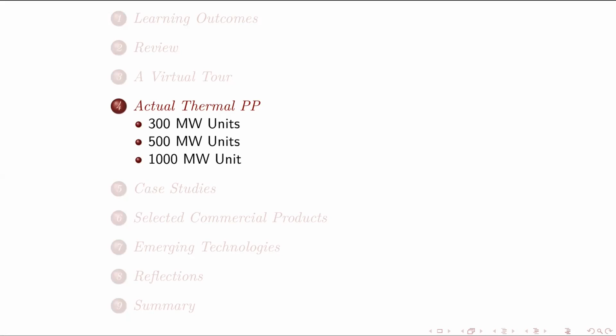Yes, Joy. Initially, when steam is created inside the boiler, it is almost 80 bars. This is the highest pressure steam generated. So since this is the highest pressure steam, it should first go to the high pressure turbine. It shouldn't go to the low pressure turbine. Thank you for your answer.